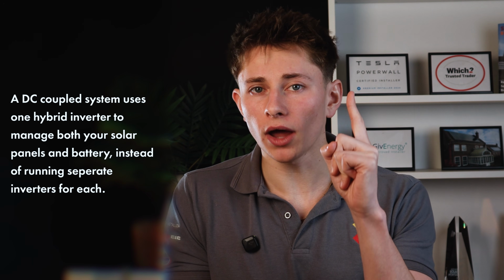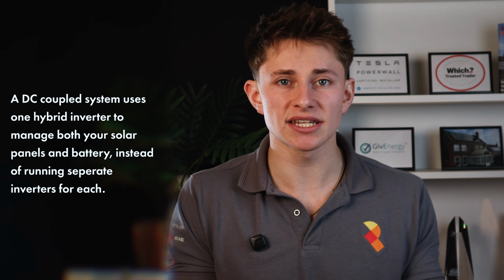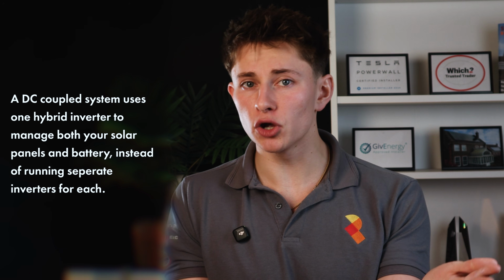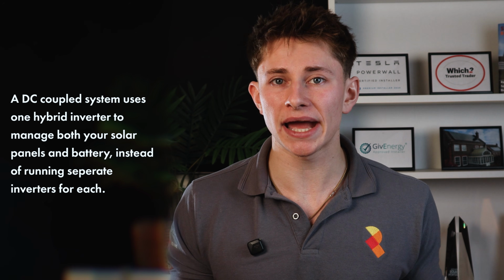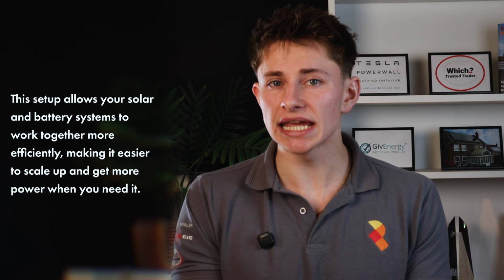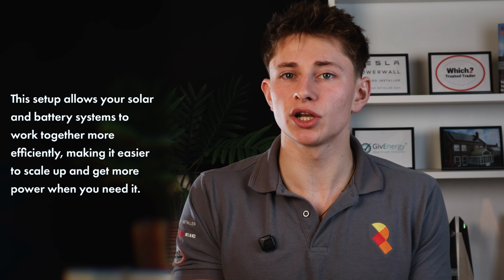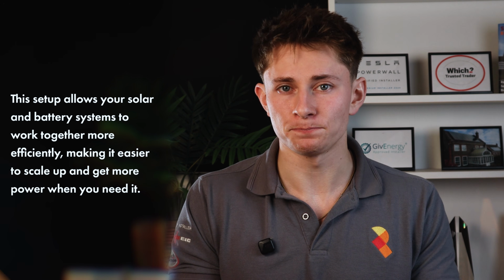Now, this brings me on to the first tip I've got with regards to how you design your solar system. And that is that if you're looking for a relatively large solar or battery system, probably anything with an inverter larger than 10 kilowatts on a single phase, then you should probably be going down the route of getting a DC coupled system, not an AC coupled system. DC coupled is where you have one hybrid inverter which manages both your solar system and battery system, as opposed to having a separate inverter for both the solar and the battery. By DC coupling, you can take advantage of much larger solar and much larger battery systems at the same time.